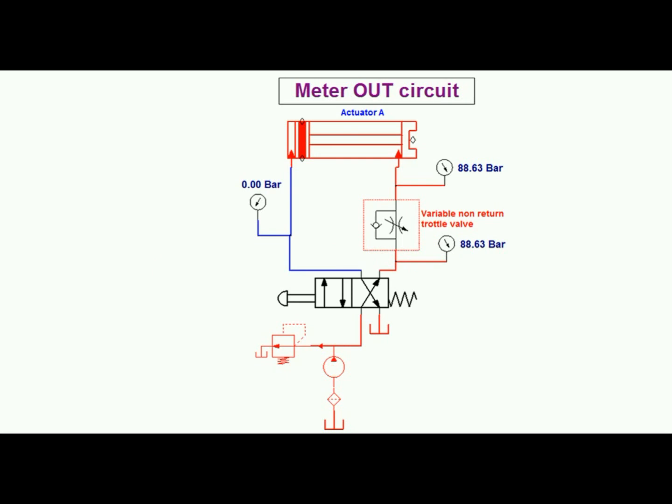The meter out circuit operation shown in figure. With a meter out circuit, a flow control valve is installed on the return side of a cylinder so that it controls a cylinder's actuation by metering its discharge flow.